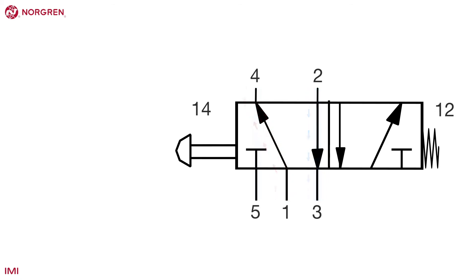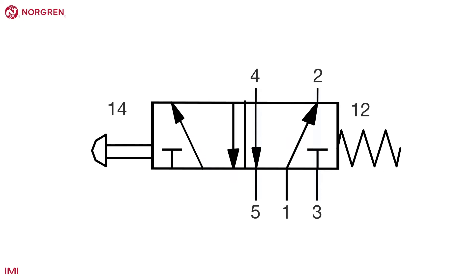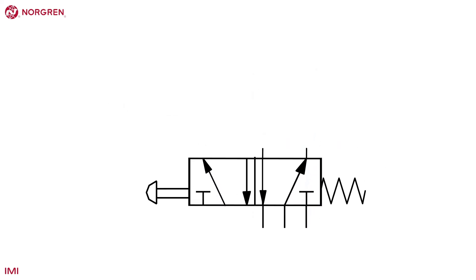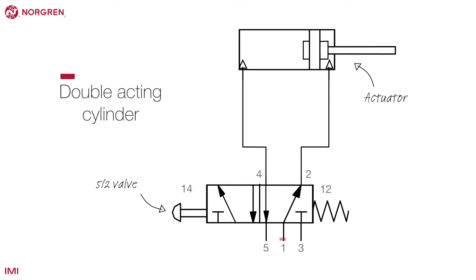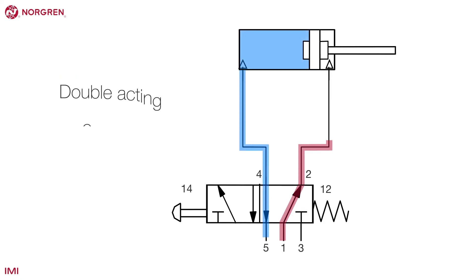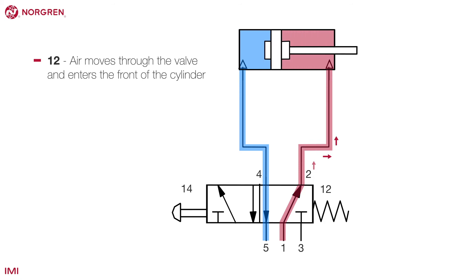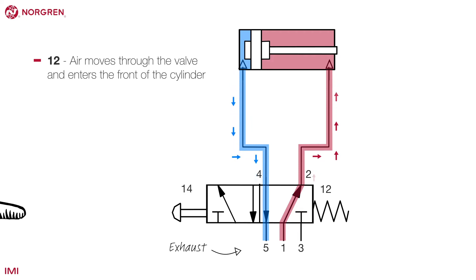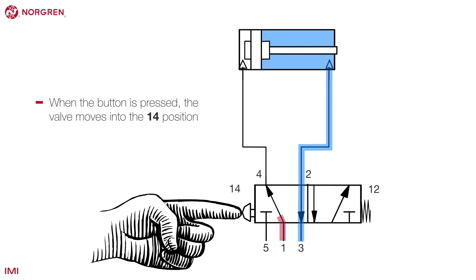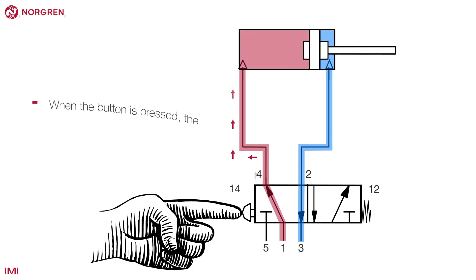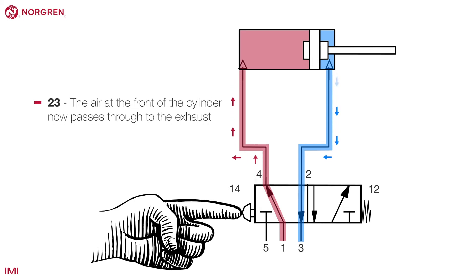A 4-2 valve is less common — these valves are similar to a 5-2 valve but share an exhaust port. Here is a diagram demonstrating a 5-2 valve operating a double-acting cylinder. In the 1-2 position, air moves through the valve and enters the front of the cylinder, pushing it inwards. Air from the back of the cylinder enters port 4 and is vented through port 5, the exhaust. When the button is pressed, the valve moves into the 1-4 position; air travels from port 4 to the back of the cylinder, pushing it forwards, and the air at the front passes back through port 2 and out of the exhaust at port 3.